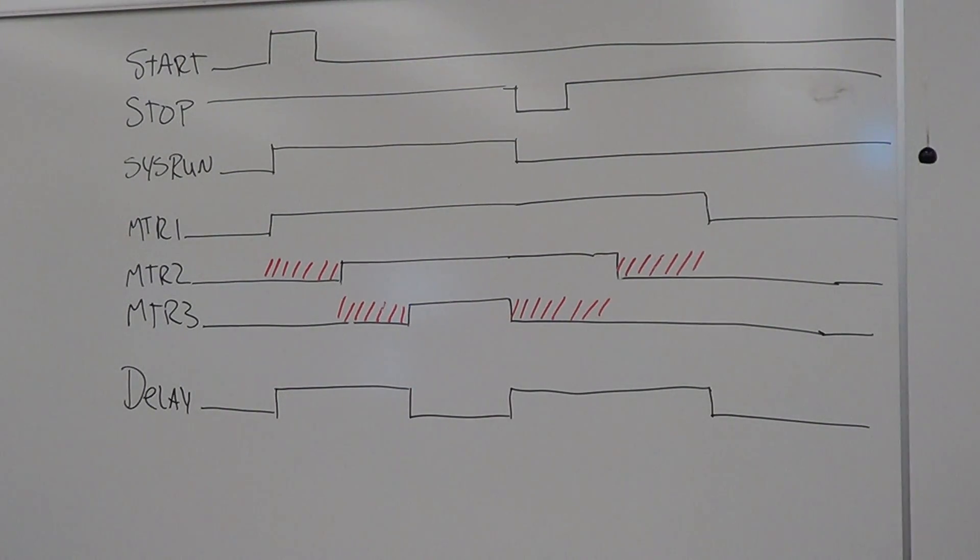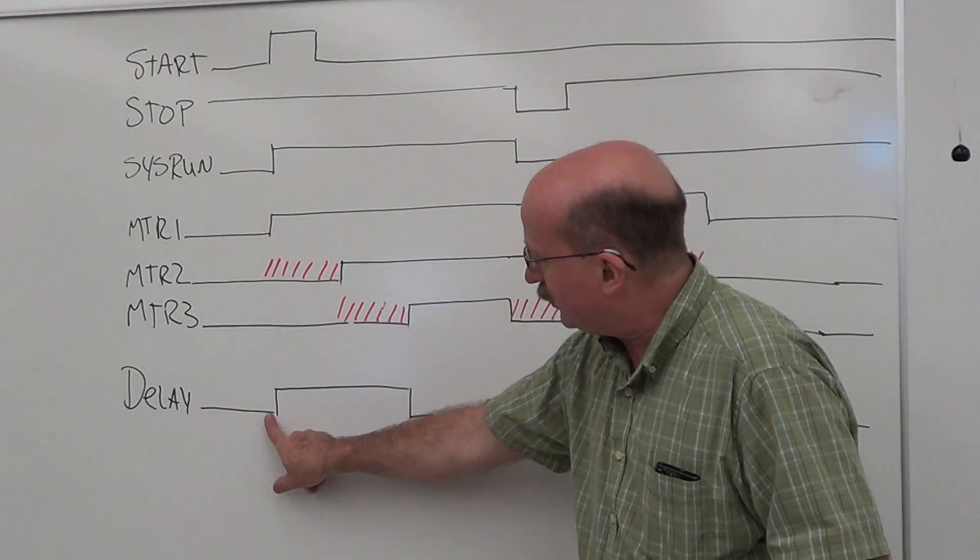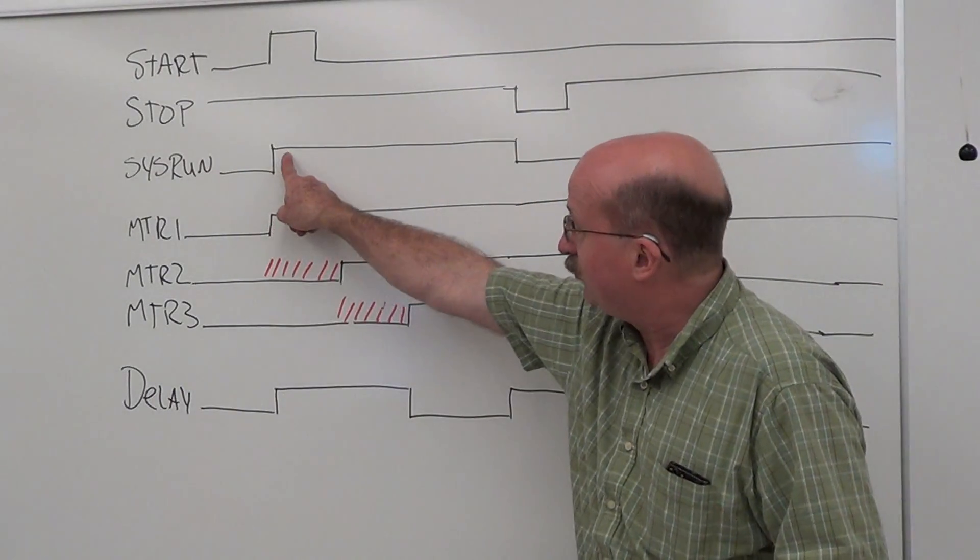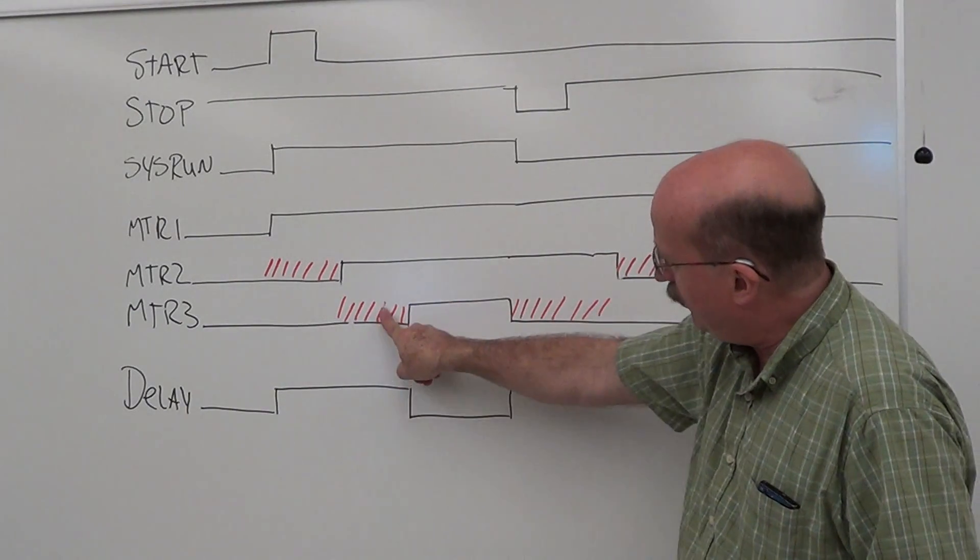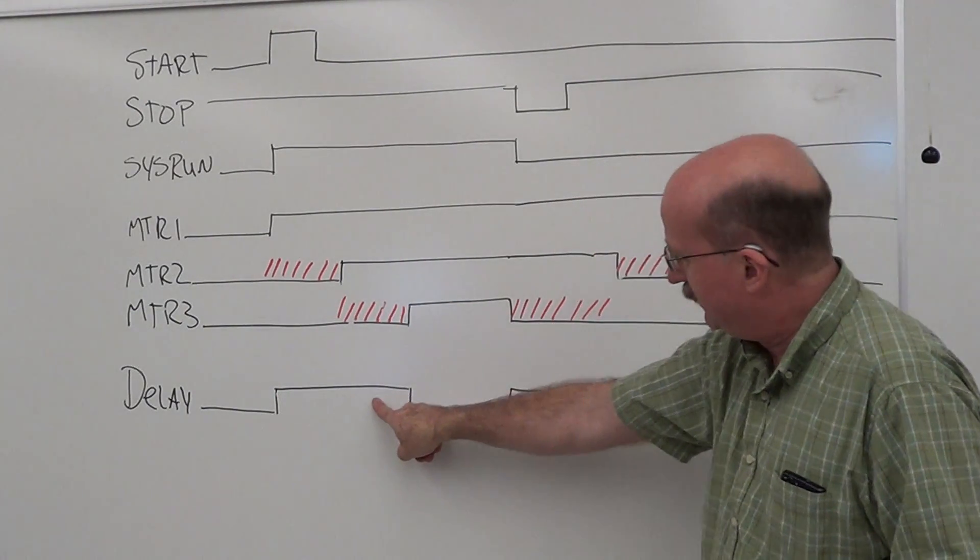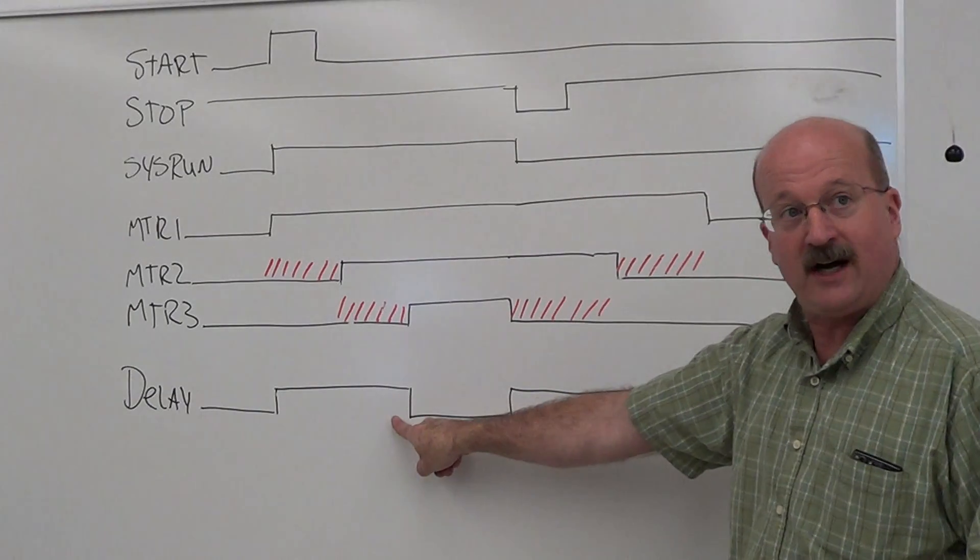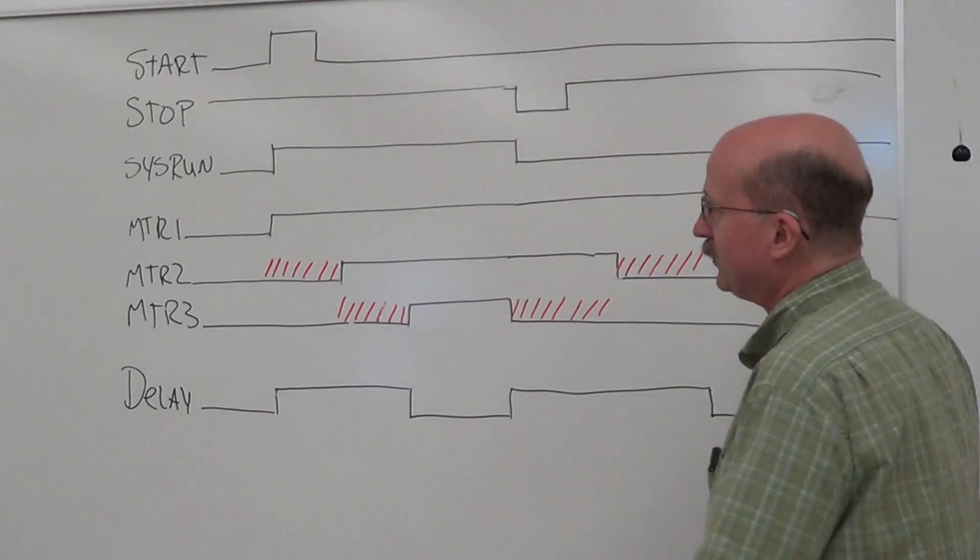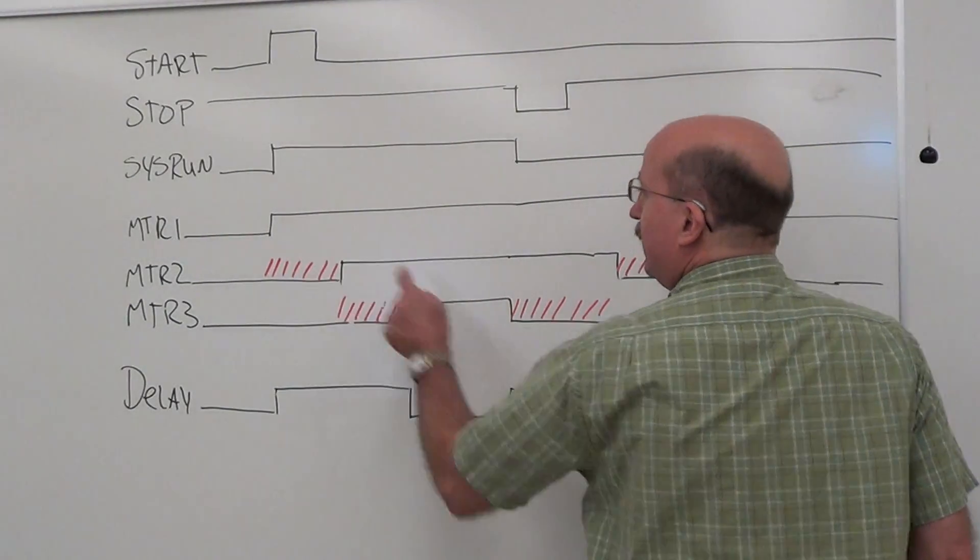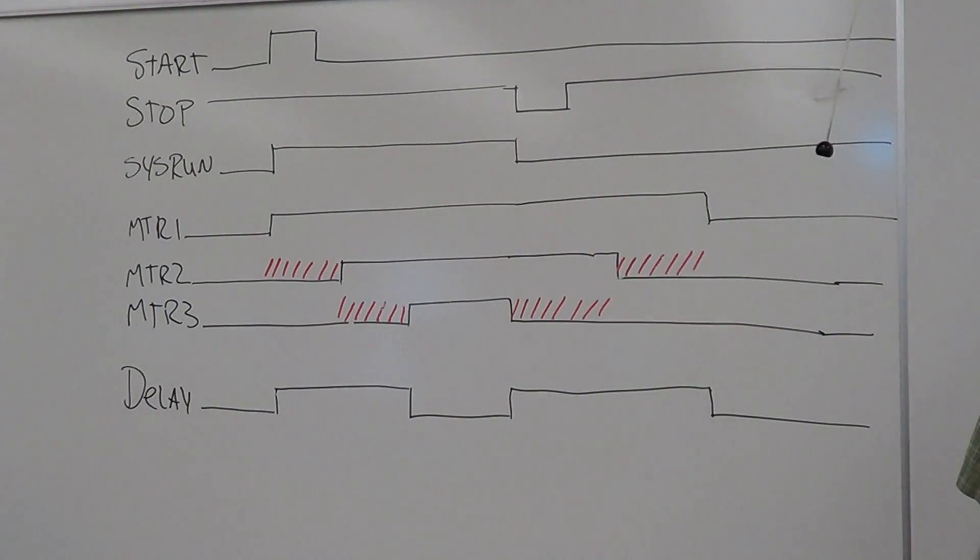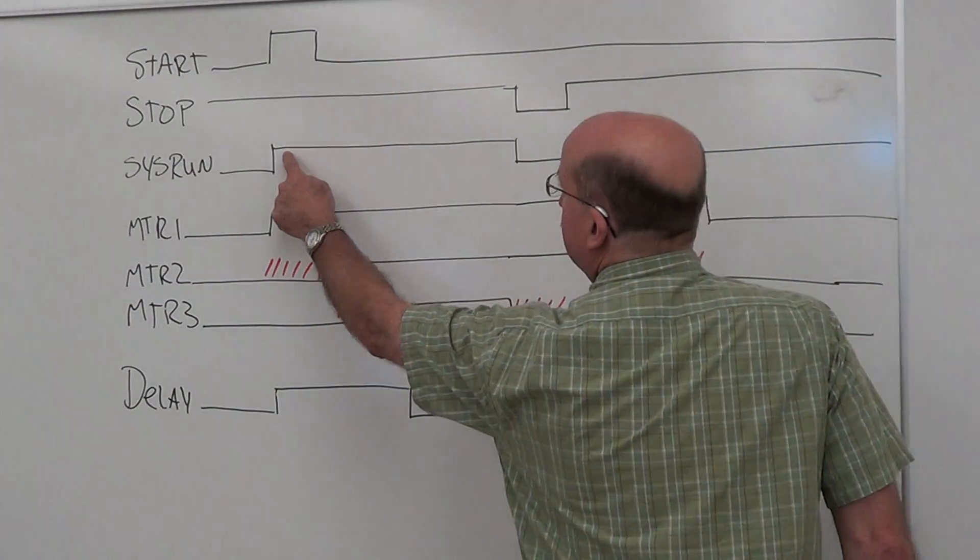Delay time later, motor two will turn on. Delay time later, motor three will turn on and the system will be all running at that point. While the motors are starting up, when sys run is on and motor three is off, during that time that's our on-delay period.